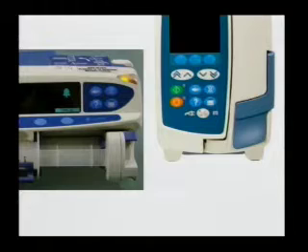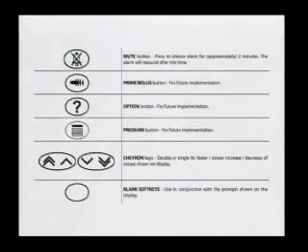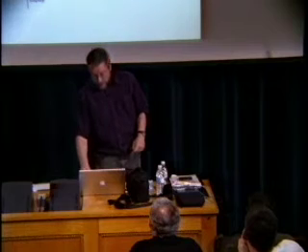Well, I'll take you out of your misery. Here's a photocopy from the manual from the infusion pump. The prime bolus button is for future implementation. The option button is for future implementation. The pressure button is for future implementation. That infusion pump costs something like £6,000, and it's got buttons on it that do nothing. And if some medical emergency happens and the nurse reaches over to press a button, that button will do nothing, and the nurse will probably think it does something.